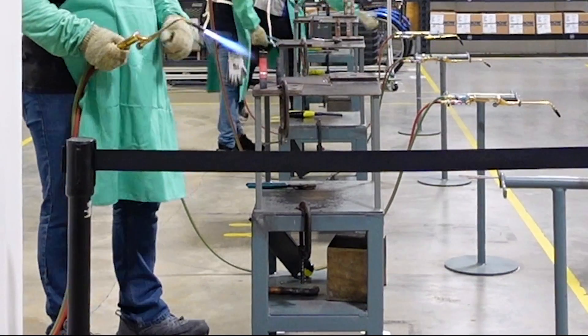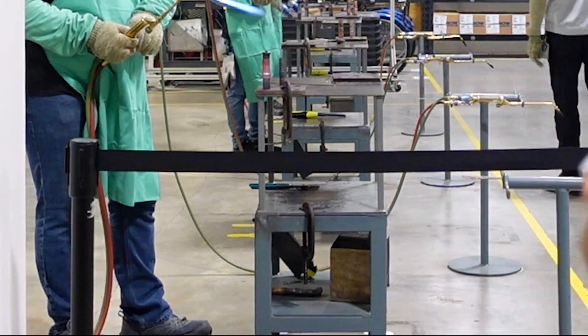The reason that we introduced Charge Integrity is because when a system is installed, we expect it to be clean, dry, and tight. There's no debris from the brazing or flaring, depending on what type of system it is. It's dry in terms of there's no external moisture. And then it's tight, meaning that it's a closed loop system — no refrigerant can get out or added in. We've got that level perfect so that we have the right level of heat transfer.